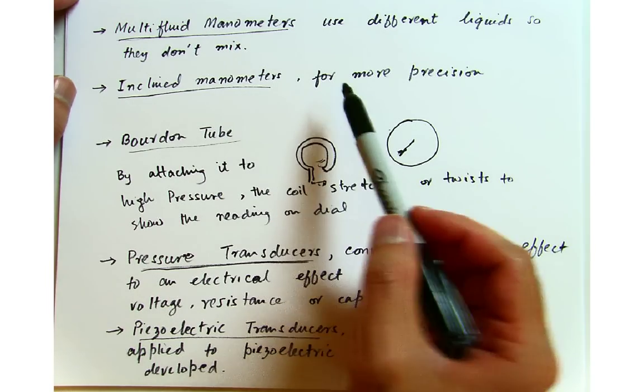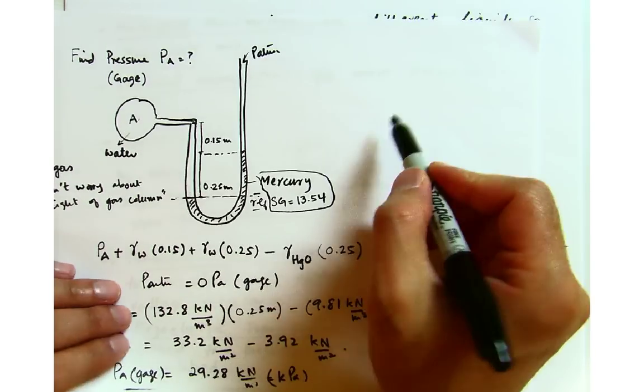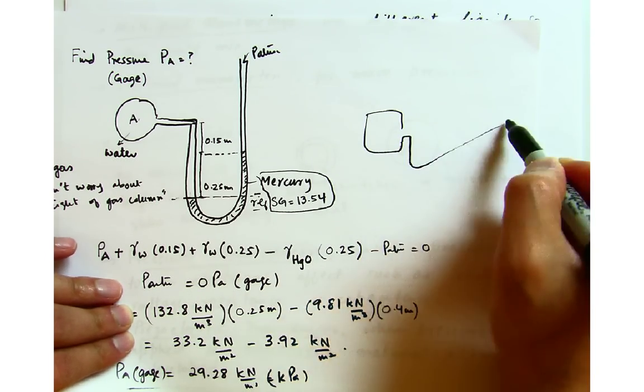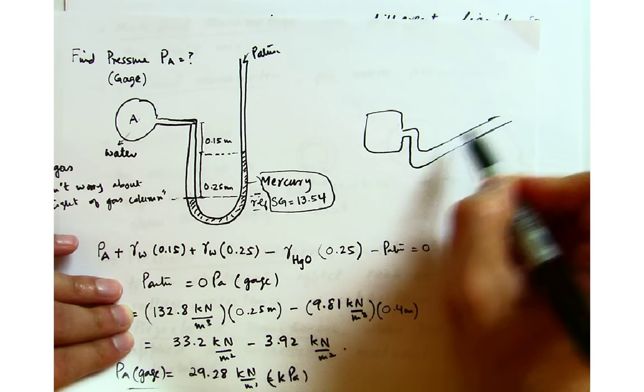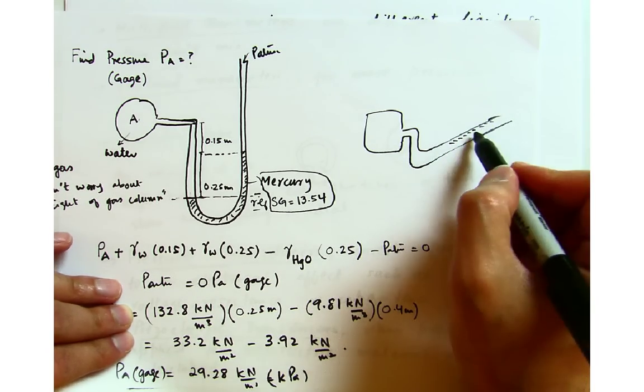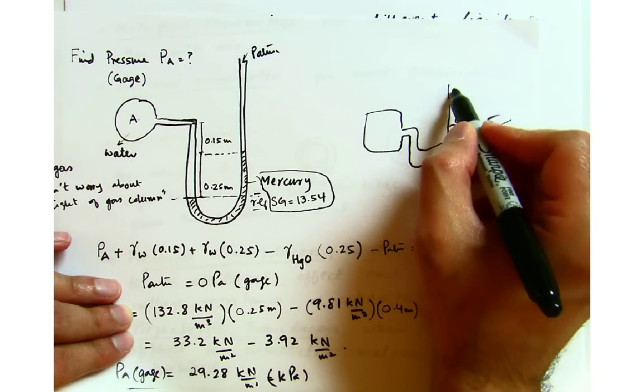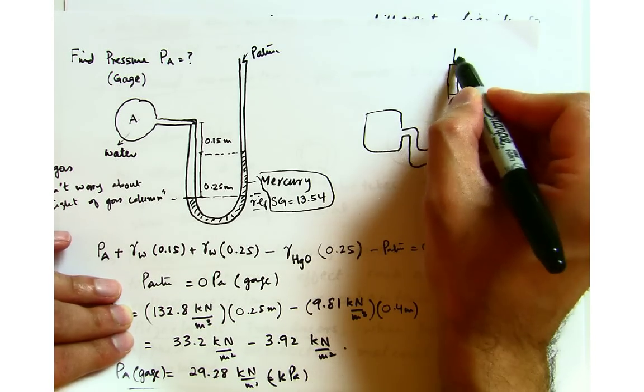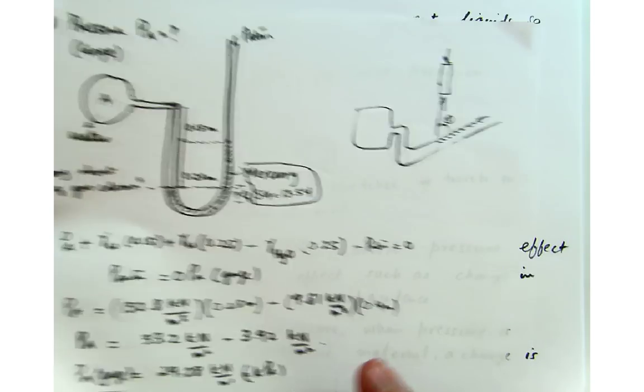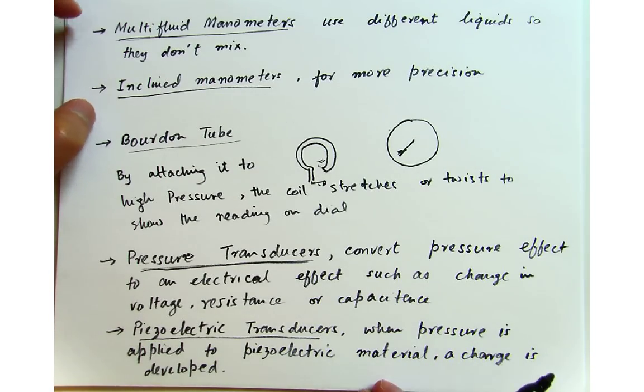There are also inclined manometers for more precision. The idea is that the manometer is more inclined, so you will have some angle and a little bit more increments, making it easier to read and more precise. The procedure is the same — you just have to take the cosine of the angle and then balance it with the weight. It will give you more increments and will be more precise. But these devices are getting kind of obsolete.